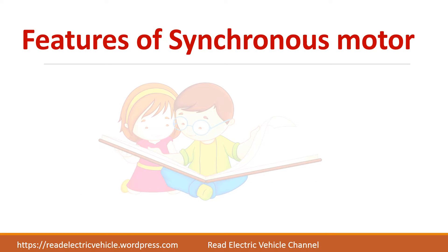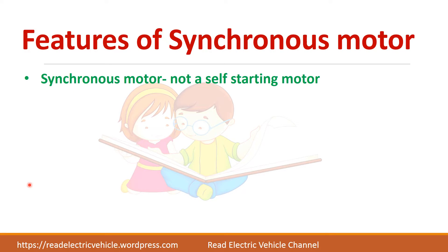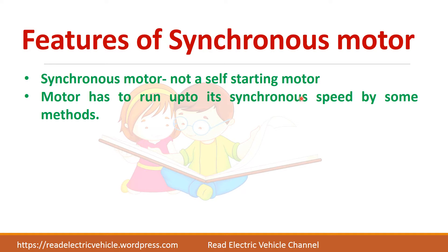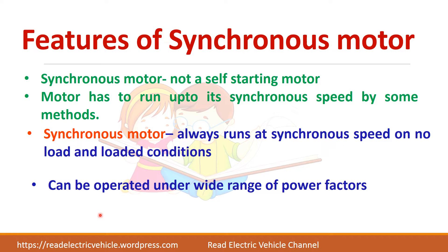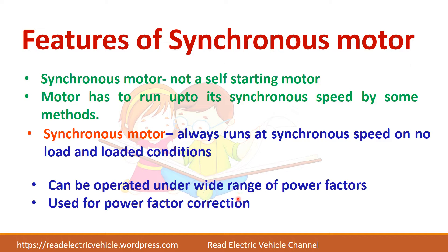Let us see the features of synchronous motor. A synchronous motor is not a self-starting motor. It has to be run up to its synchronous speed by some arrangement. Synchronous motor will always run at synchronous speed and it can be operated under a wide range of power factor. That is the main application of synchronous motor — it is used for power factor correction.